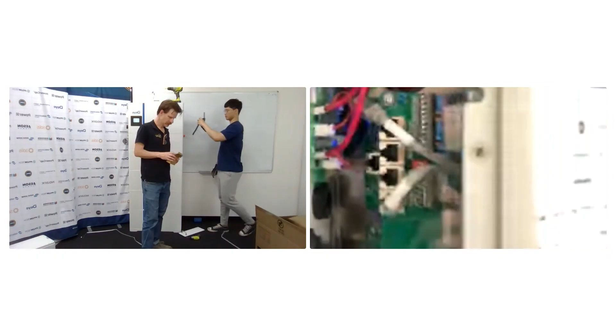When you're commissioning these, whether you're using the meter or the CT, a really easy mistake to make is getting the CT the wrong way around. So I recommend that when you put it together, just put a big load on and watch the direction of the power. If it's not going the right way, turn the CT around, or you can just flip the CT wires around the other way. It's an important thing to check before you leave site, because it will do all sorts of wacky stuff if it thinks it's exporting when it's not.